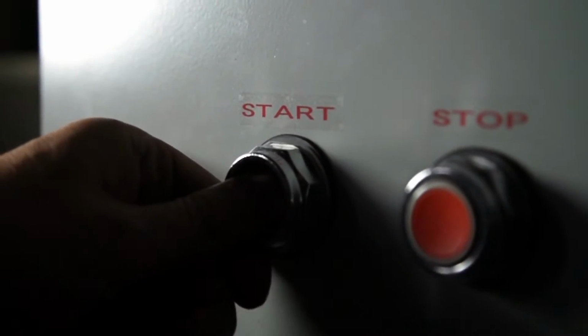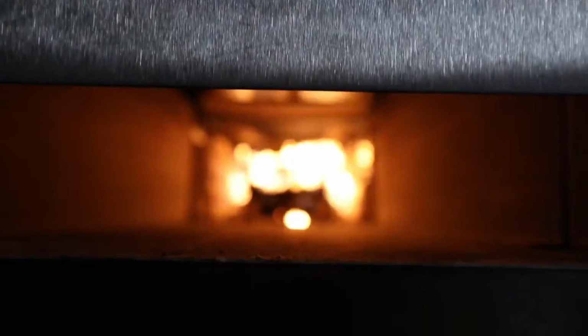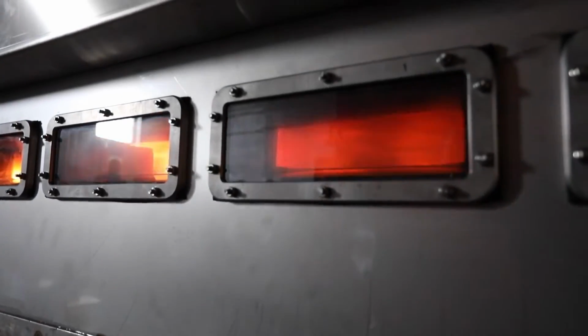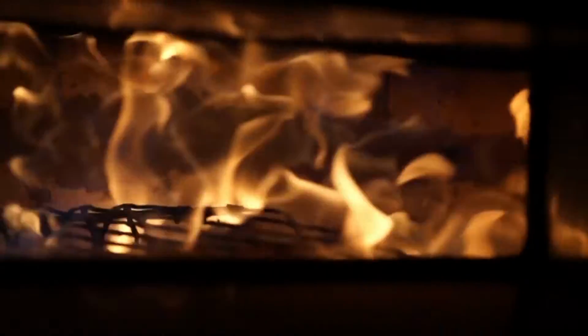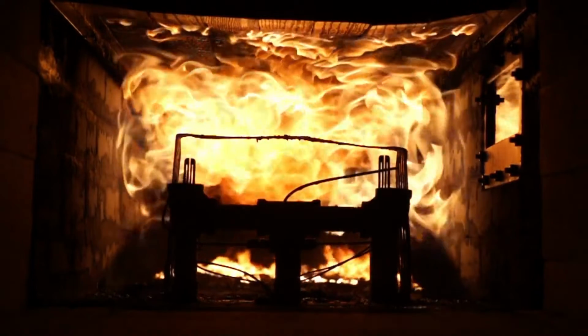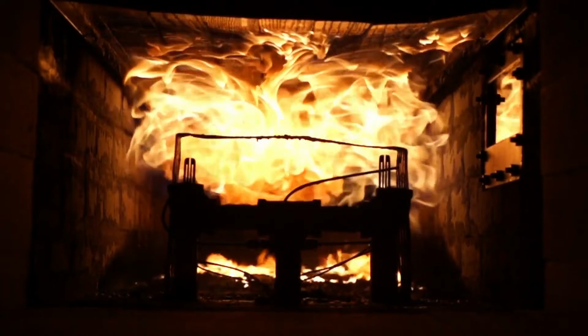The test material is then subjected to extreme gas flame exposure from two natural gas burners. A 3-inch opening near the end of the tunnel, as well as a regulated exhaust fan, allows air to be drawn through the tunnel at a steady rate, ensuring that the igniting flames are able to spread naturally across the face of the test specimen.